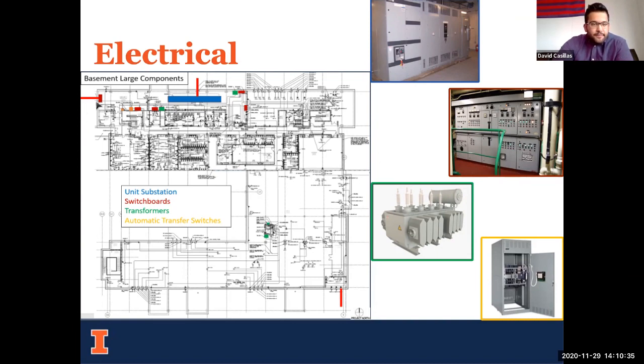This tie-in comes from the emergency generator located around here—I'll show it in the next slide. This duct bank leads to here, connecting to a switchboard, which then connects to the automatic transfer switches shown here. These control the use of the generator, and then connect back to the unit substation.